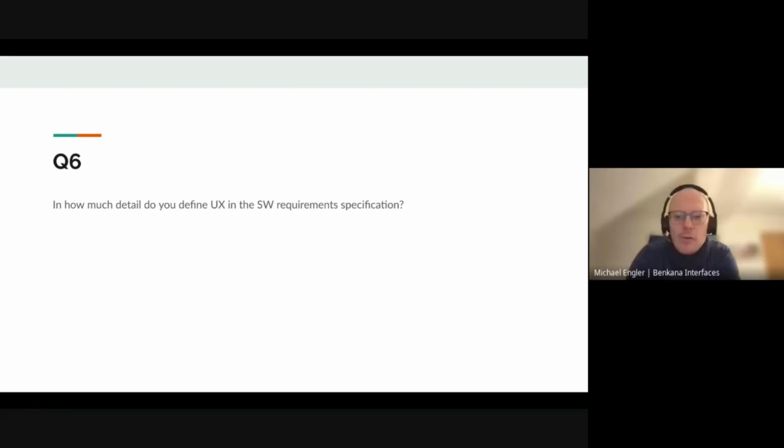Yeah, I already said... when I redo files, which happens a lot lately because of MDR, so we're reworking usability engineering files, that never happens to anyone I know, but of you. But hey, if you do that, I always go through, because the notified bodies don't have any clue. I say, okay, we're going through your existing specifications and we mark everything that is user interface related, and then we are done. So that's the easiest way of doing it. That's the cheap way. You get through every audit. It's very difficult for a notified body to say, hey, that's the wrong way to do it. They obviously can't do it, so that's the cheap way.